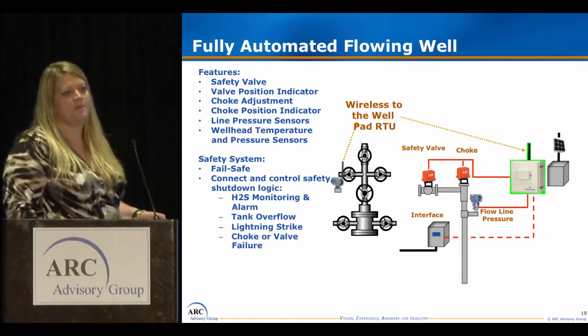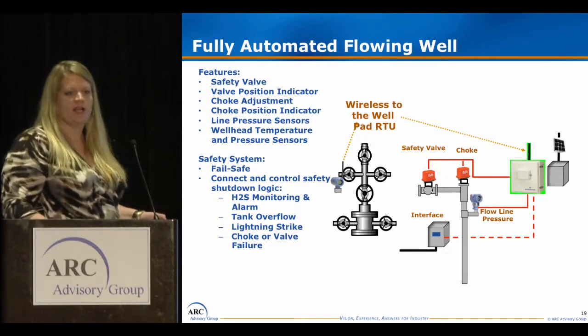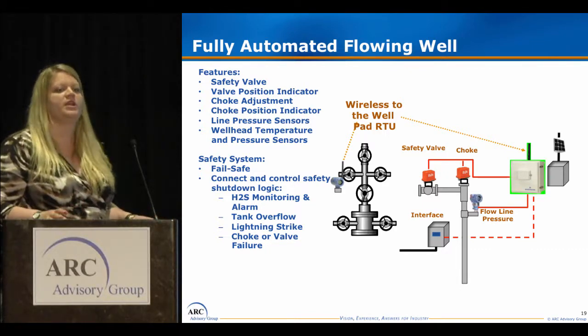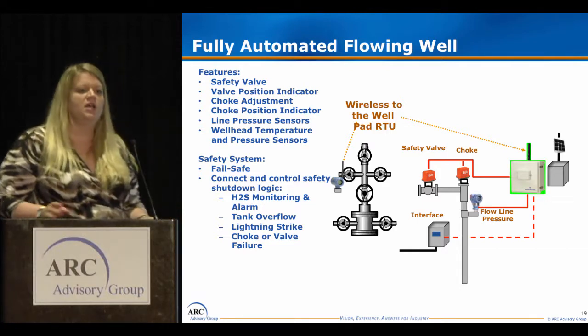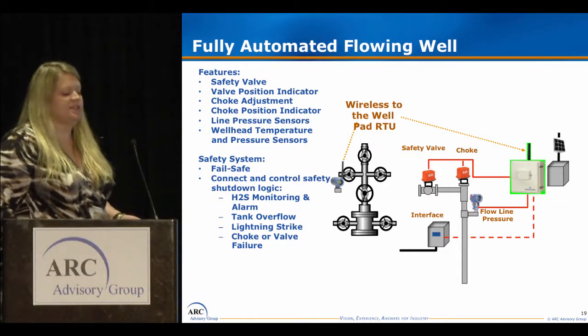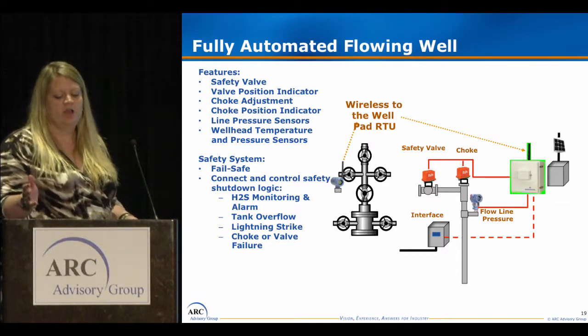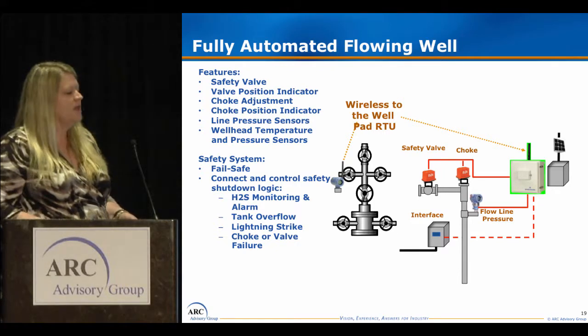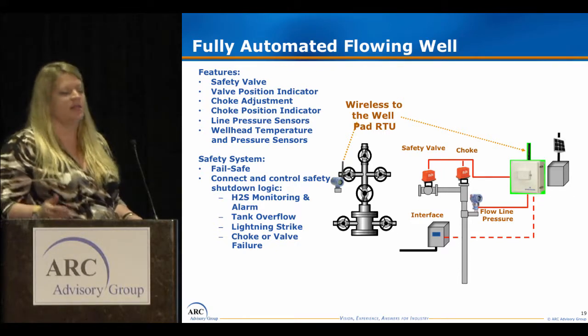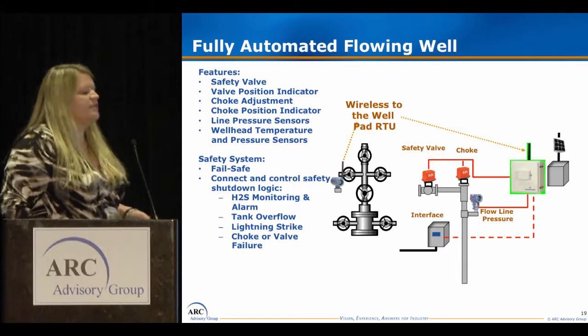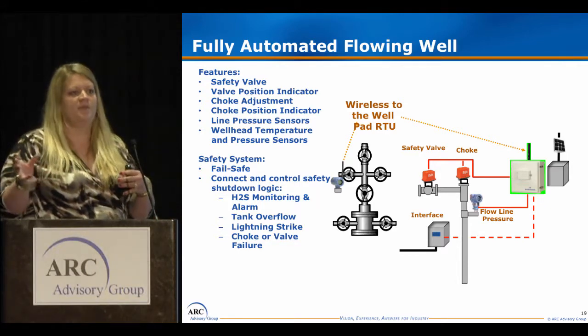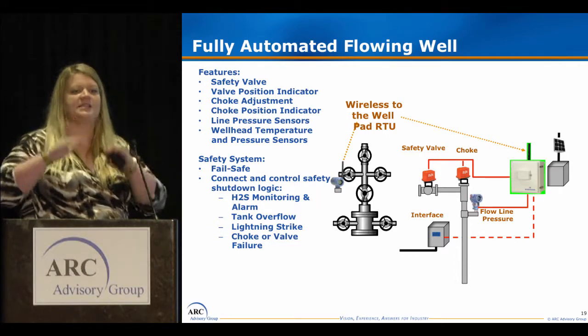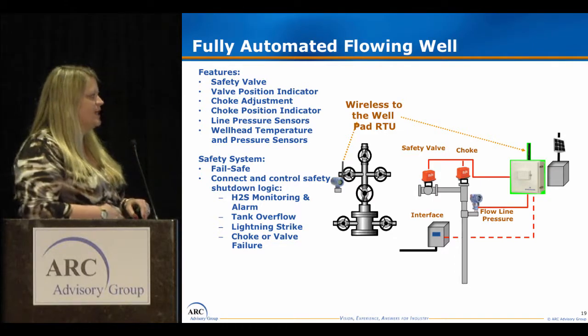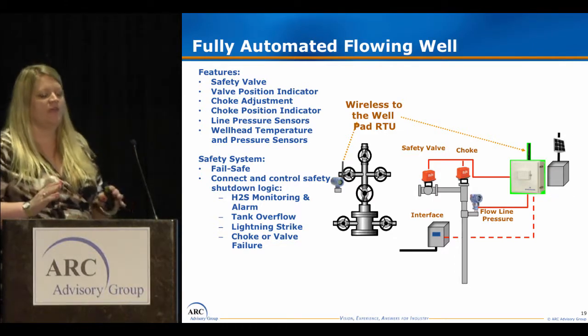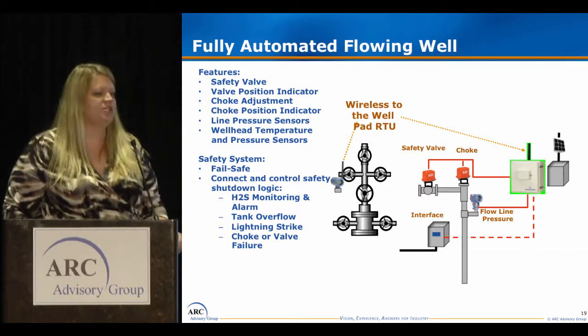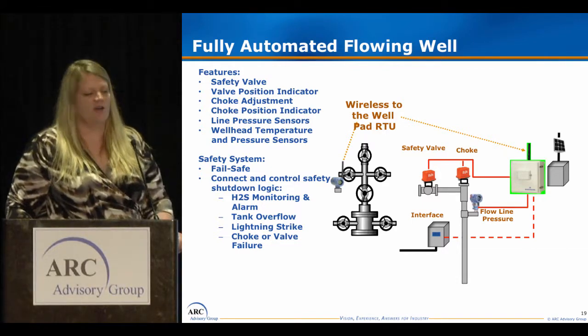A choke we could control electronically - we're starting to install those on all our gas lift wells, and that's been great because I can open the choke a certain amount and increase the gas lift rate. Eventually we can plug that into a program with a pre-built algorithm, set the points and limits of operation for that well, and it just optimizes itself.